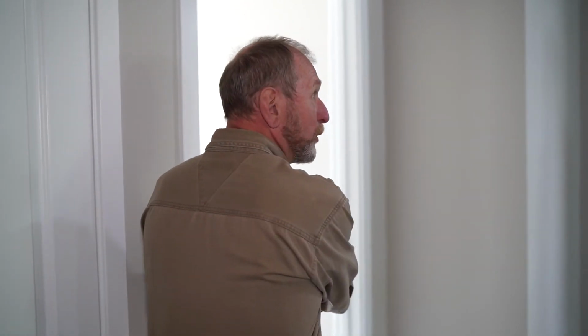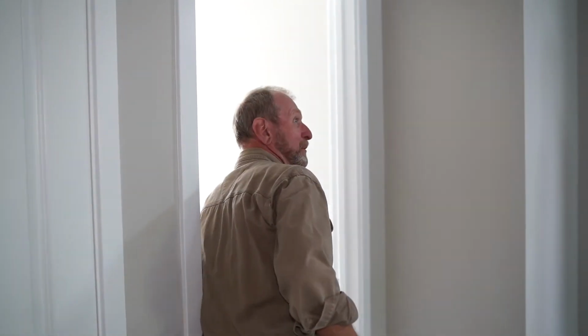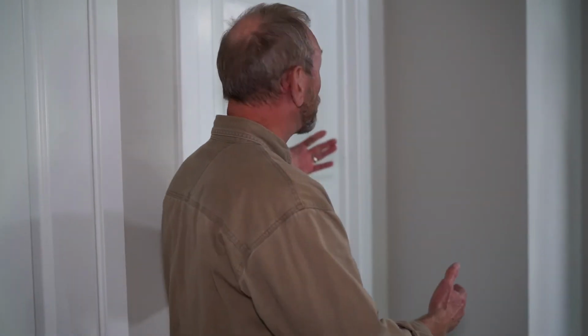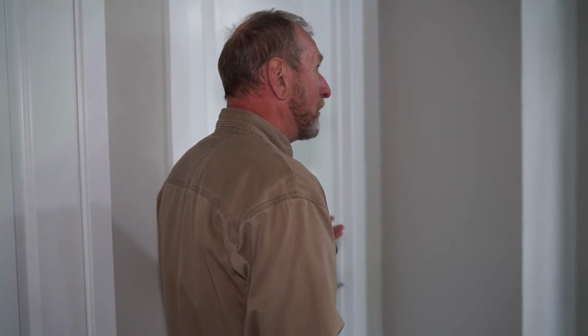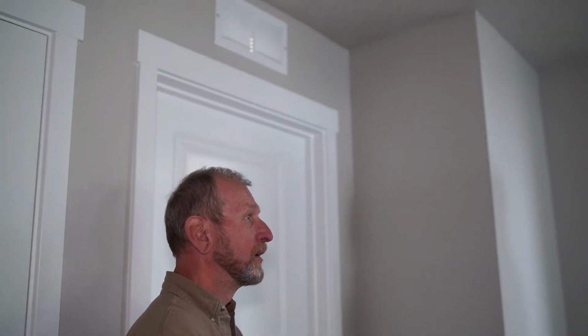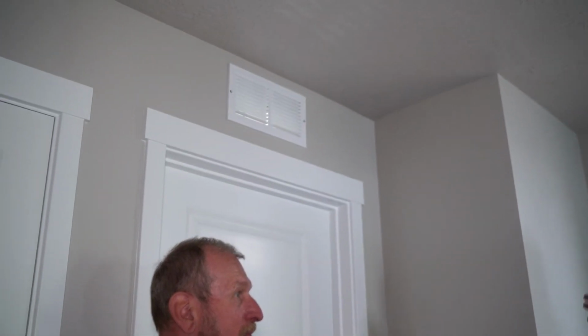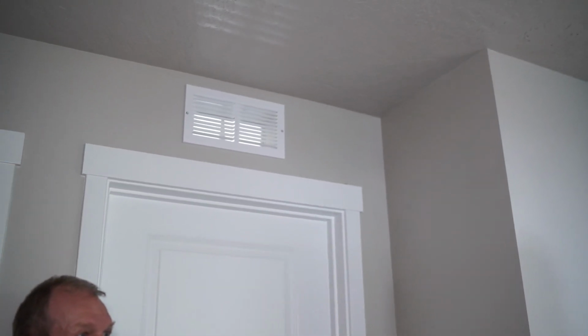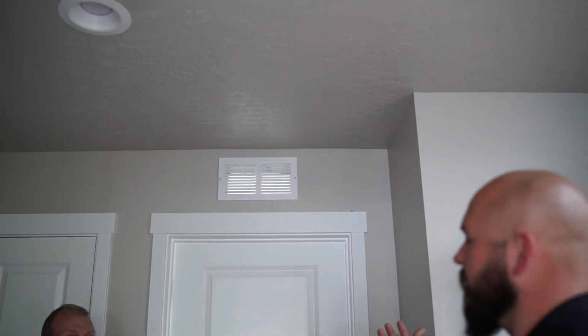With forced air heating systems, you're blowing a lot of air into rooms, and sometimes people close the door. That traps all the air behind that door. How can we solve that problem? In this situation, we have a centralized return air in the hallway, and above it we have what we call transfer grills. So as that door shuts, it still allows a return air pathway back to the unit.